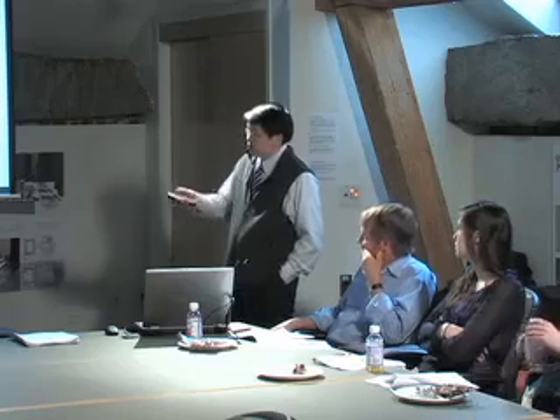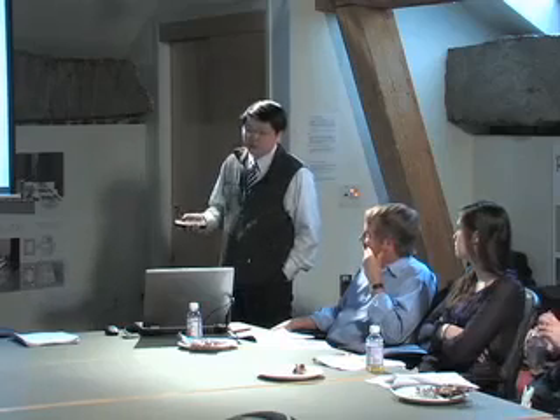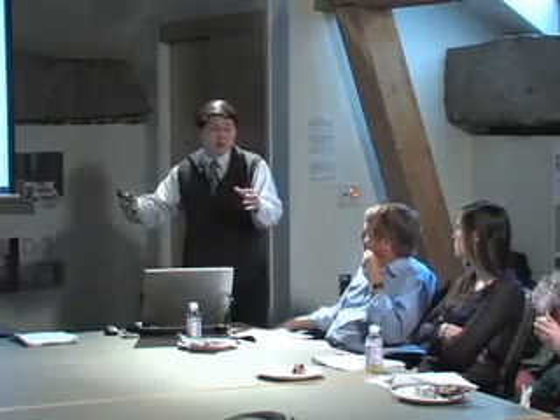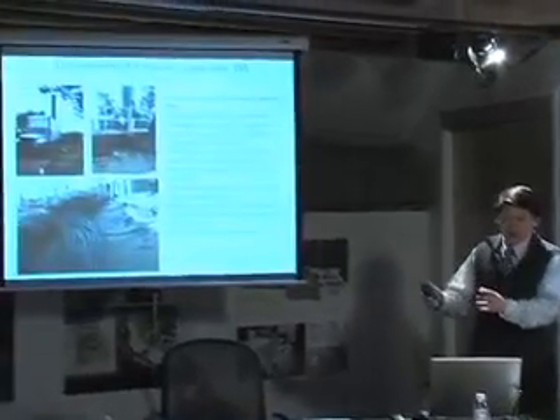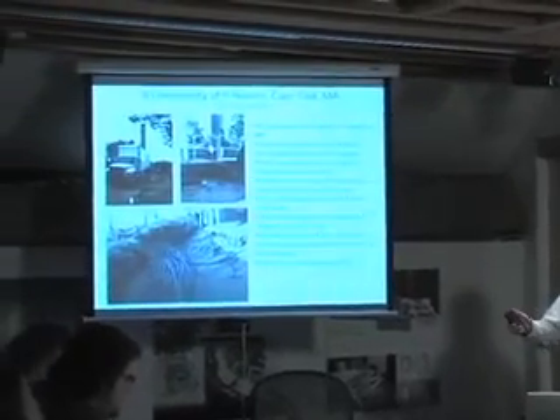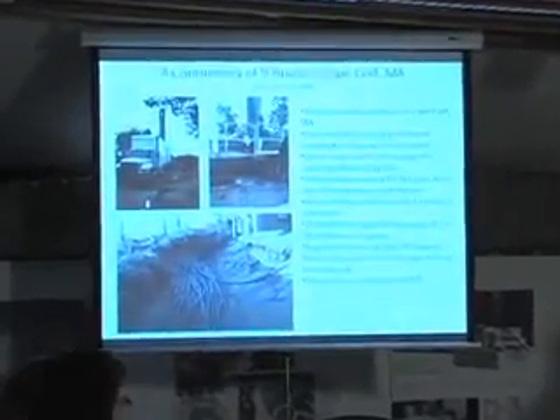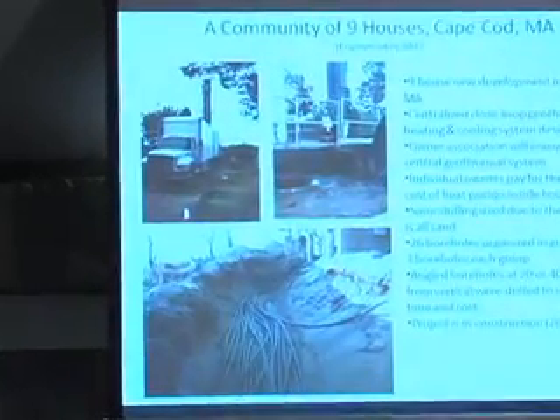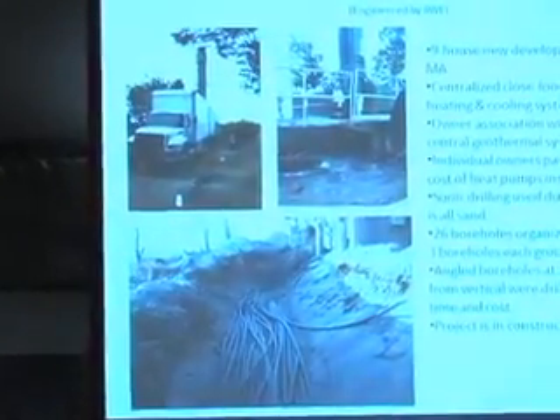Now, the reason we designed the system this way, with a central ground loop system, is like I showed you in that slide where you have multiple heat pumps. Sometimes not every heat pump is running at a certain time. When not all heat pumps are running, you're not taking so much heat out of the ground during the heating season, so the ground temperature is warmer. And warmer ground temperature means a higher heat pump efficiency, so it's very efficient.